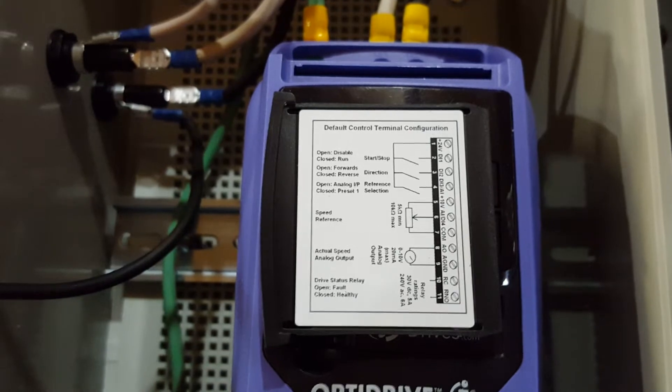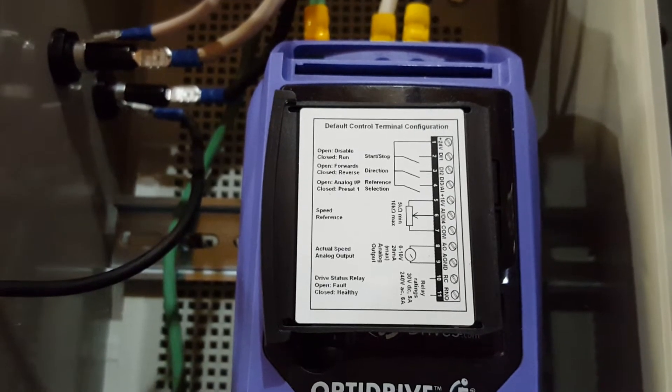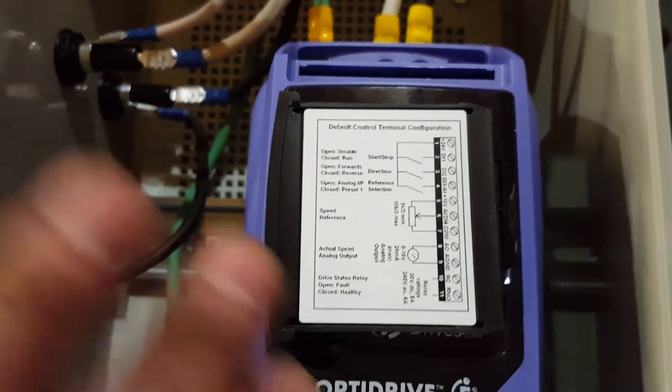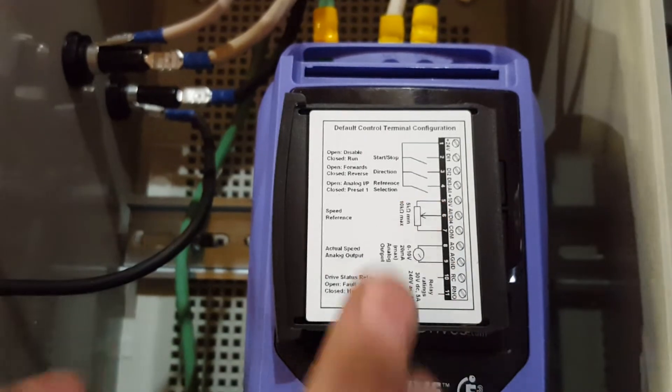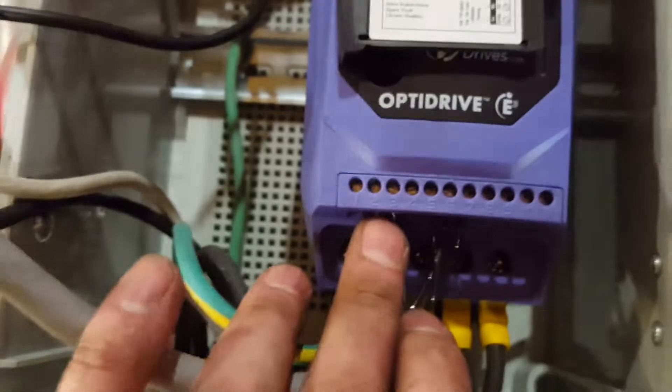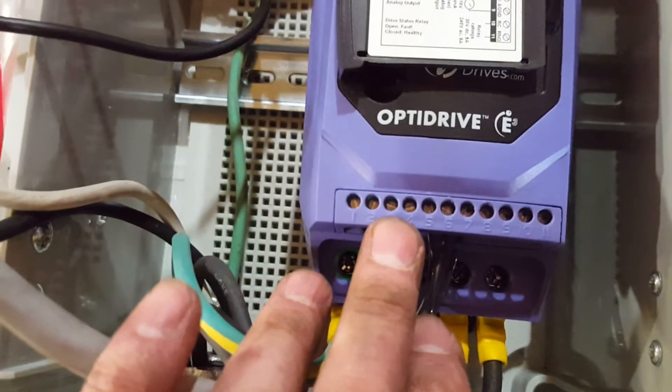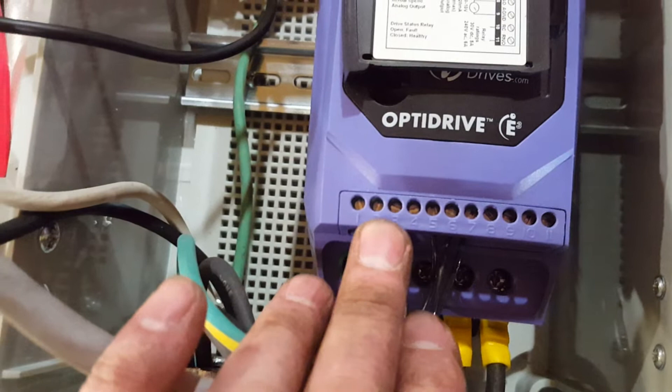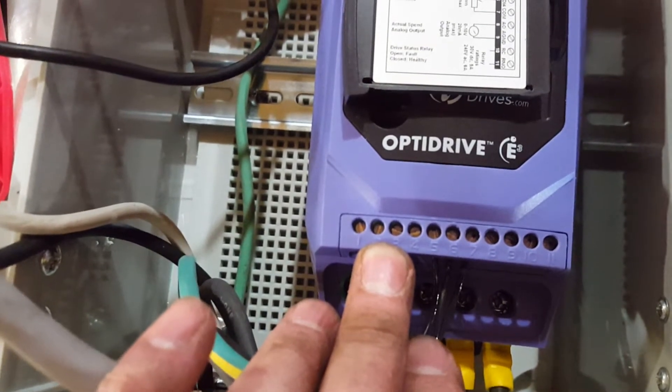If you want to switch directions, you simply close the directional contact, which is pin number three. So basically that would be the equivalent of jumping a wire from three to two while it's running. That switches directions.